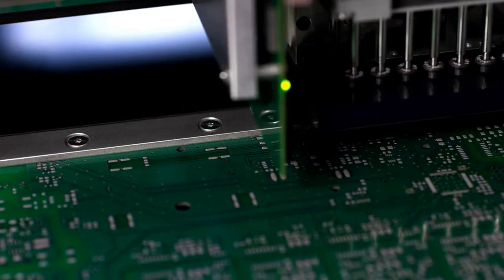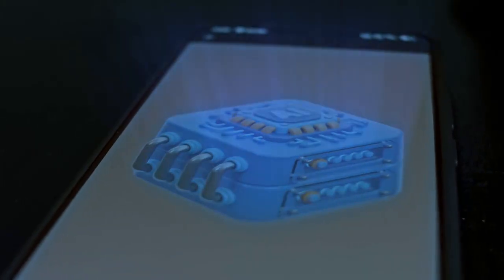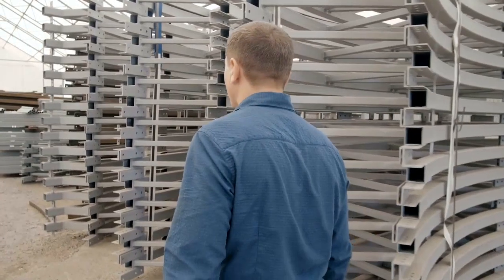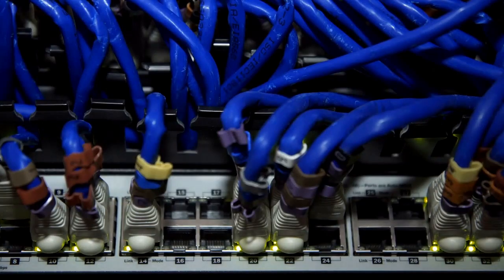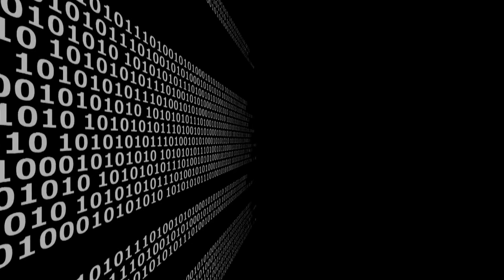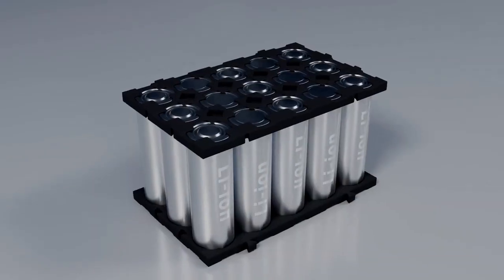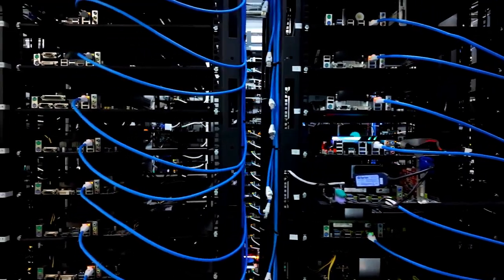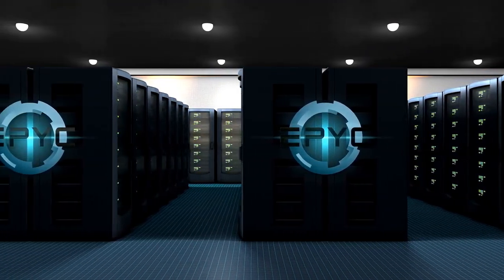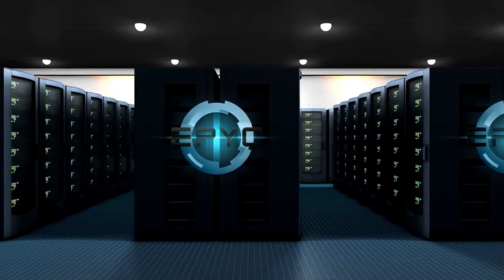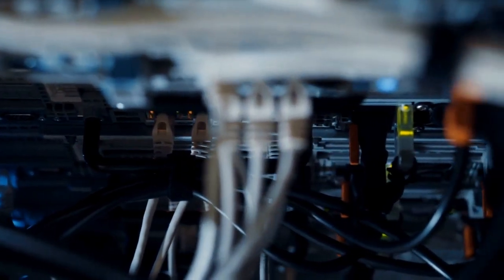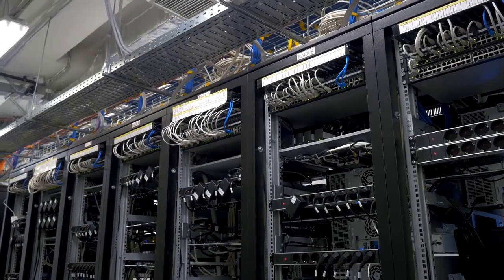However, the problem compounds further, because these chips do not operate in isolation. To achieve the massive, coordinated throughput required for generative artificial intelligence, these chips are densely clustered together to minimize communication latency. When millions of dollars of hardware are calculating probabilities simultaneously, physical distance between chips translates directly to latency delays. Therefore, the architectural imperative is to pack as many chips as physically possible into the smallest possible space. This design philosophy culminates in systems like the NVIDIA GB200 NVL72. This exascale computing behemoth links 72 highly advanced Blackwell chips and 36 Grace processing units into a single, monolithic, rack-scale architecture connected via copper cabling. This single unified rack demands an astonishing 120 kilowatts to 132 kilowatts of power, representing a nearly 10 times increase over the rack densities of just a few years prior.